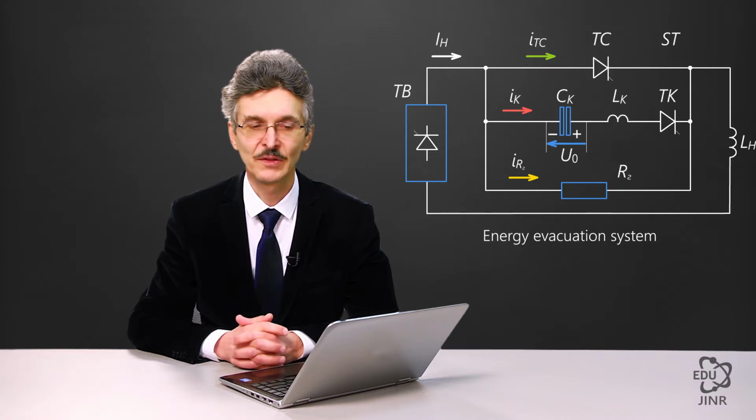Under normal operation of the accelerator, the current, which is supplied from a source to a load, flows through a power thyristor. When a normal transition phase is detected, a signal is sent to the commutation thyristor, and the energy that had been accumulated in a special capacity locks out the power thyristor, and the current is shifted to the chain containing field suppression resistance.